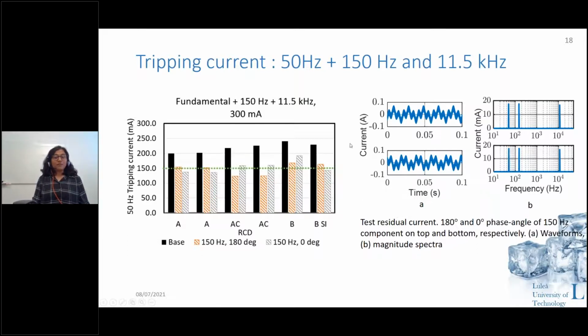100%. So if you see, on the left hand side for 300 milliampere RCDs, this is the result for the 50 hertz tripping current that is present. So you can see that the RCDs should trip from 150 hertz and above. But for type A RCDs here, in case of 150 hertz and 0 degrees, the RCDs trip below the 150 hertz component, and this is false tripping of the RCDs. If we just consider the 50 hertz component, then it is a false trip for the RCDs.